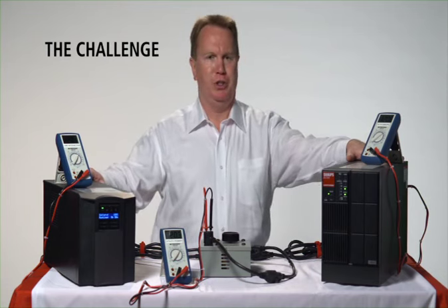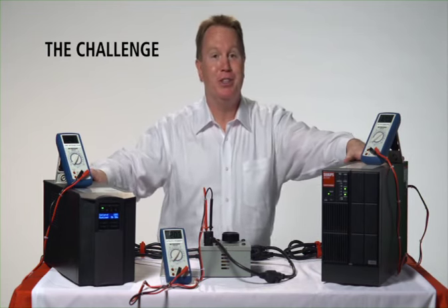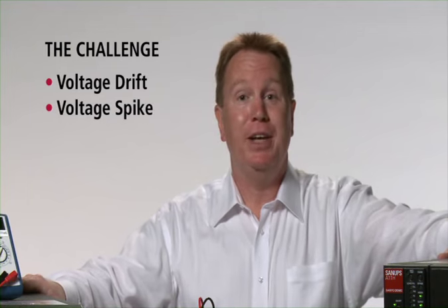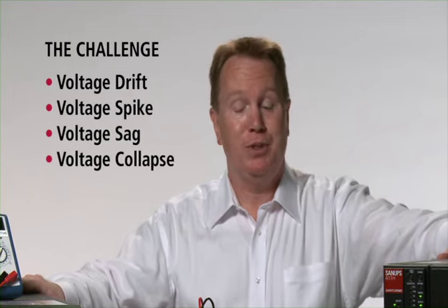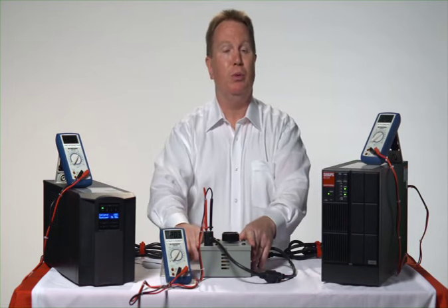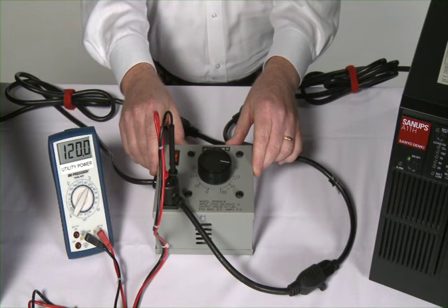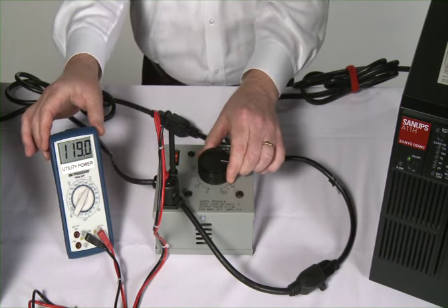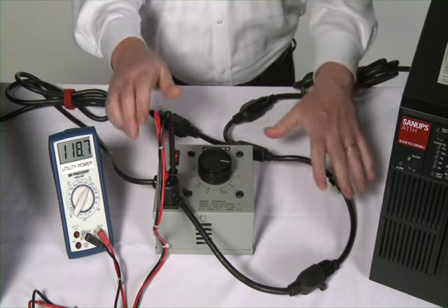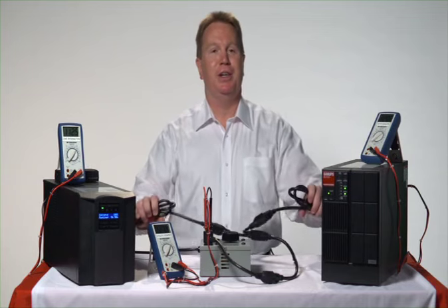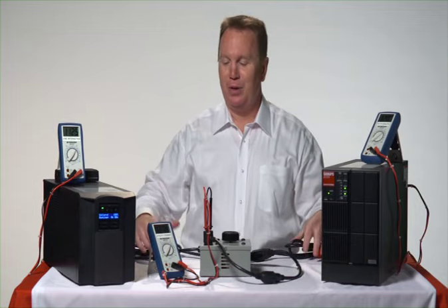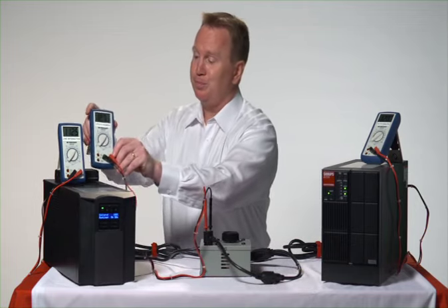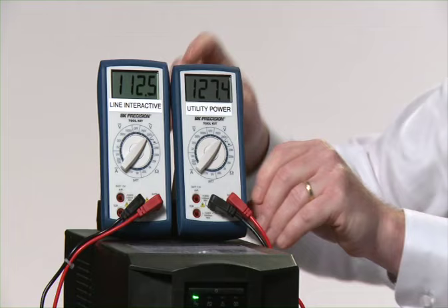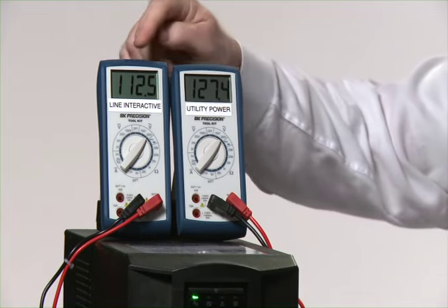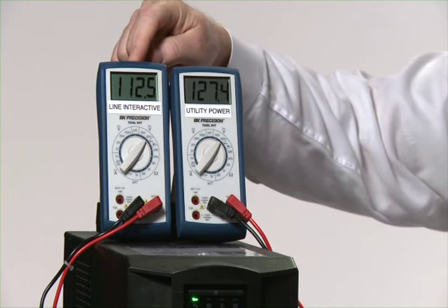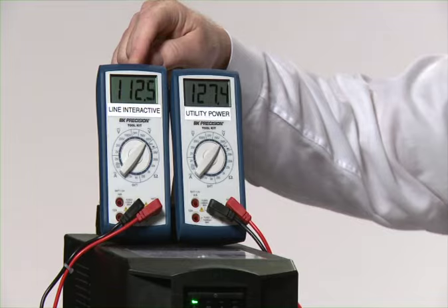Today we're going to challenge both of these UPSs with 4 common power conditions: voltage drift, voltage spike, voltage sag, and voltage collapse. We are supplying both of these UPSs with a variable transformer to simulate adjustable utility source voltage as indicated by this meter. The output of this variable transformer is connected to both UPSs. Both of these units are seeing identical voltage throughout this demonstration. Let's see how our line interactive unit performs. Once again, we have this meter indicating our utility input voltage. This meter is indicating the line interactive output voltage that your precision equipment is seeing.